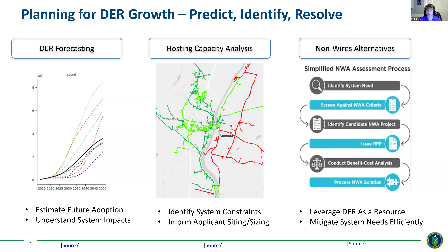As I mentioned, we're going to dive into hosting capacity and non-wires alternatives today. So, hosting capacity as an overview: this is the amount of DER, generally of a certain type though not always, that can be interconnected to the system without basically making things worse, without having to make system upgrades. So if I have 5 megawatts of hosting capacity, I can add 5 megawatts of generation before things start to break down. Generally these analyses are based on a subset of planning criteria, the same ones studied in DER interconnection for where upgrades are needed.